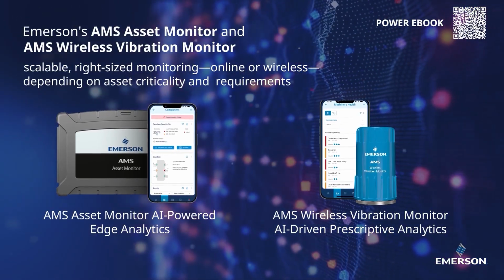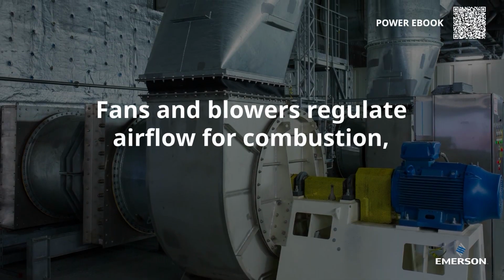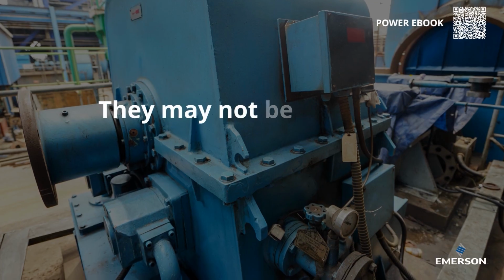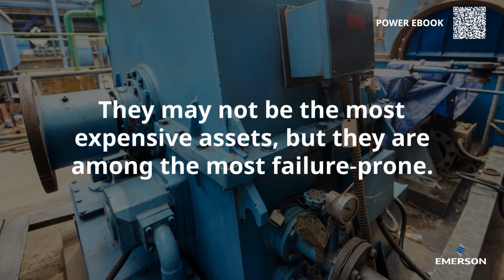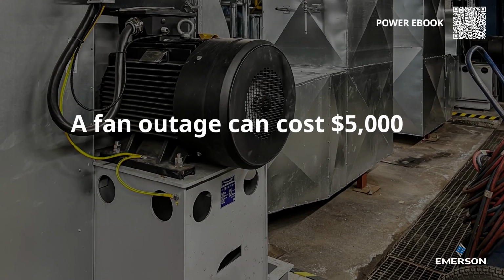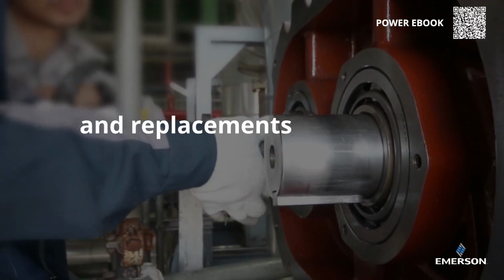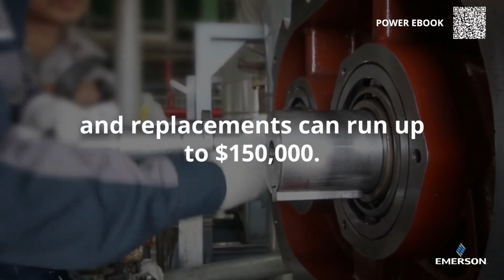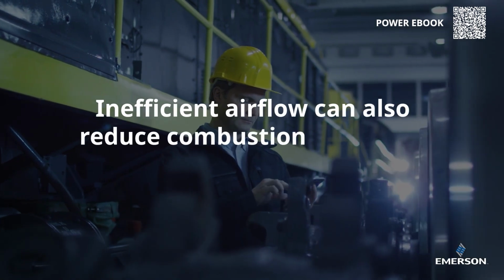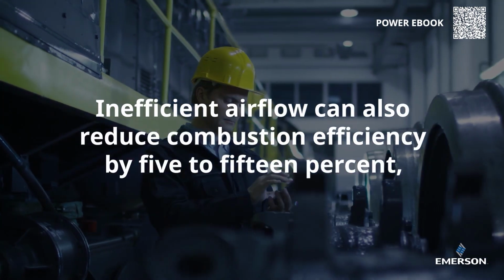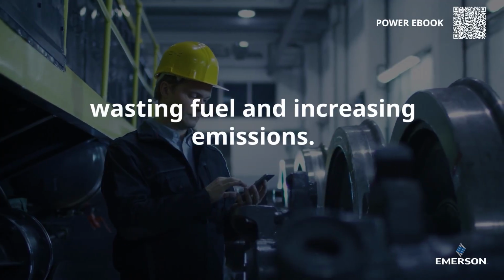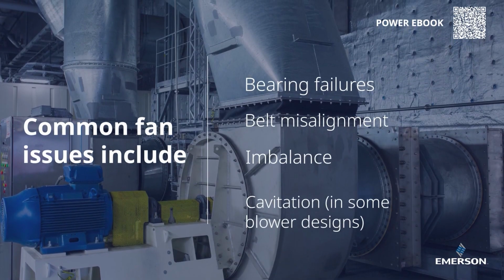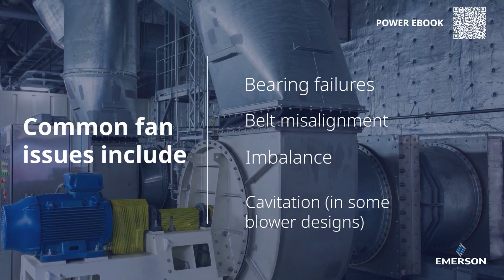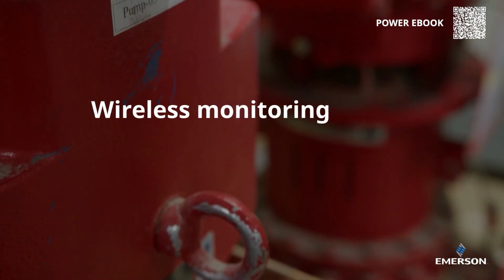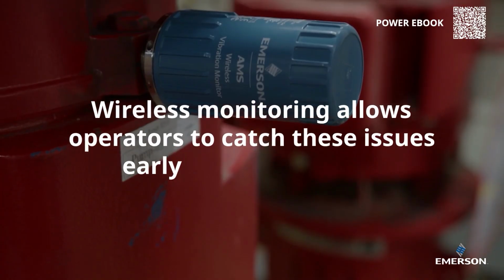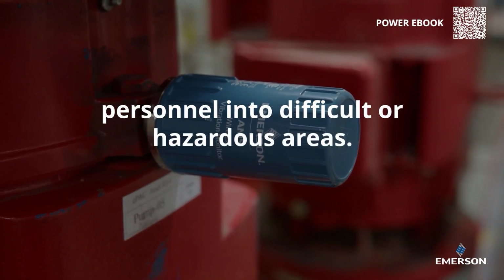Fans and blowers regulate airflow for combustion, cooling, and ventilation. They may not be the most expensive assets, but they are among the most failure-prone. A fan outage can cost $5,000 to $20,000 per day, and replacements can run up to $150,000. Inefficient airflow can also reduce combustion efficiency by 5 to 15%, wasting fuel and increasing emissions. Common fan issues include bearing failures, belt misalignment, imbalance, and in some blower designs, cavitation. Wireless monitoring allows operators to catch these issues early, without sending personnel into difficult or hazardous areas.